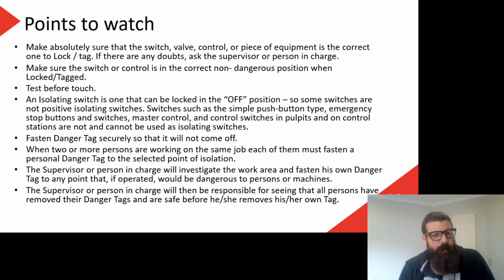Couple of points to watch. Make sure that the switch, valve, control or piece of equipment is the correct one to lock or tag. If there are any doubts, ask the supervisor or person in charge. Make sure the switch or control is in the correct non-dangerous position when locked and tagged. Yeah, the last thing we want to do is accidentally lock something on rather than off, although you will find that most lockable isolators and valves, you can only lock them when they're off. You can't lock them on.